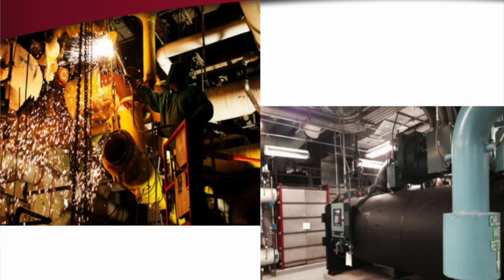Here's a little picture of our chiller plant. As mentioned before, we have a river water intake. We use that river water as the heat rejection and a free energy source for waterside economizer. About 90% of the air handling systems were able to incorporate airside economizer, but there were some systems where the original MERs were so tight we couldn't get the louvers into the historic structure to make airside work. And then those systems have waterside.